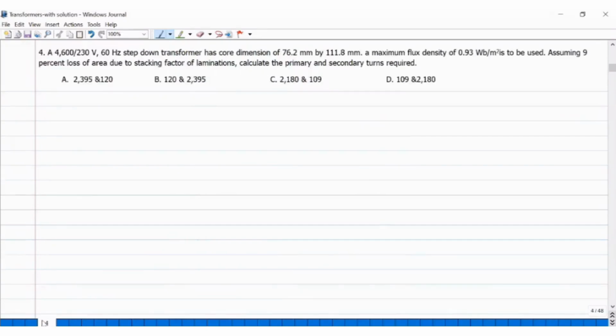Okay, number 4: a 4,600 by 230 volt, 60 Hz step-down transformer has core dimensions of 76.2 millimeters by 111.8 millimeters. A maximum flux density of 0.93 Weber per square meter is to be used, assuming 9% loss of area due to stacking factor of laminations.